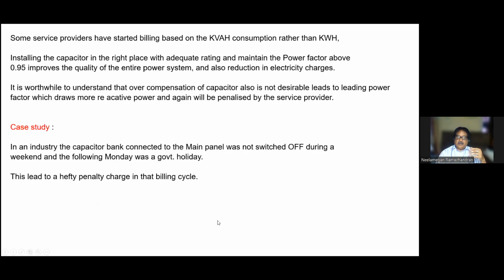So I had a very bitter experience. Before putting in an automatic power control panel, we were doing it manually, and the shift person forgot to switch off the capacitor bank on a Saturday, and Monday was Republic Day. So for 2 days it was running at a leading power factor, and we had to pay nearly 1 lakh in penalty, because the day after Republic Day, the 27th, is when the meter reading is taken. So we had a very bad experience with that.